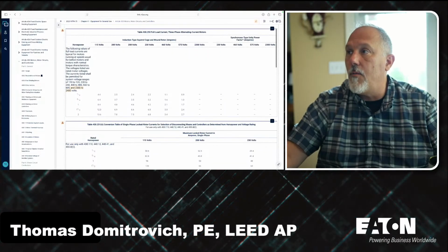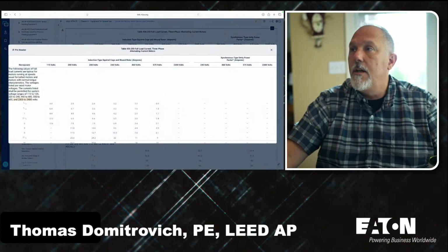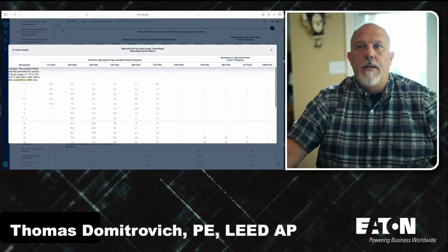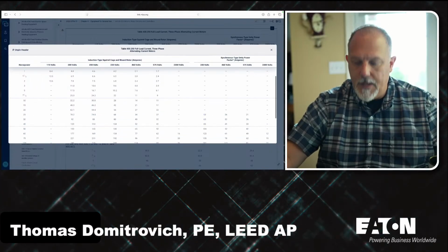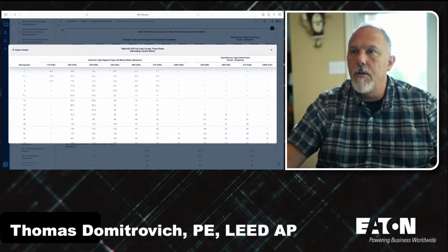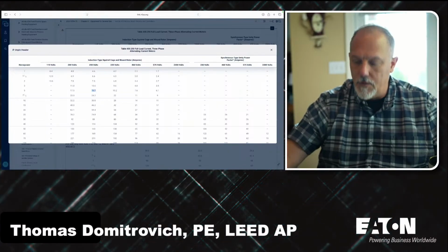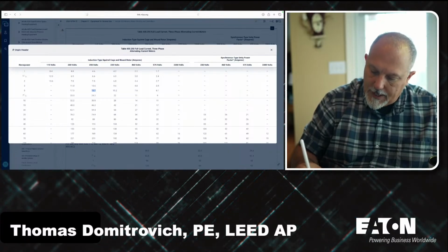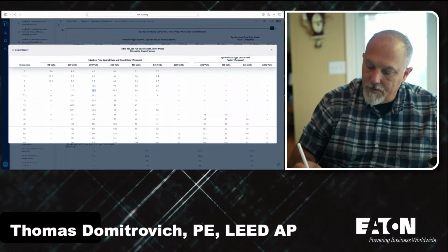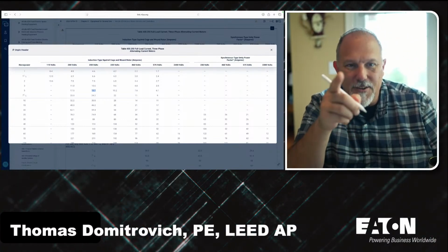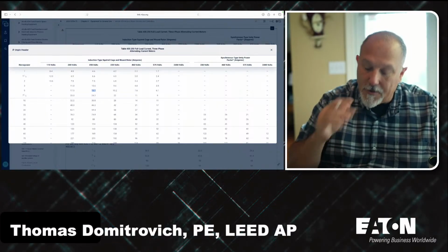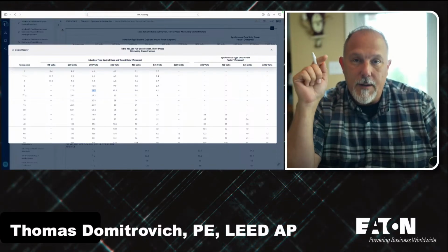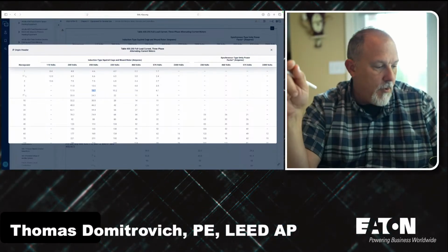Oh, I can watch this trick. If you didn't know this about NFPA LiNK, it is a saver. Pin the header. 208. I have a 5 horsepower motor, 16.7 full load amps. 16.7 full load amps. Redondo taught me this, full load current, because this is from the table, right, Redondo? I'm going to use full load current from the table.